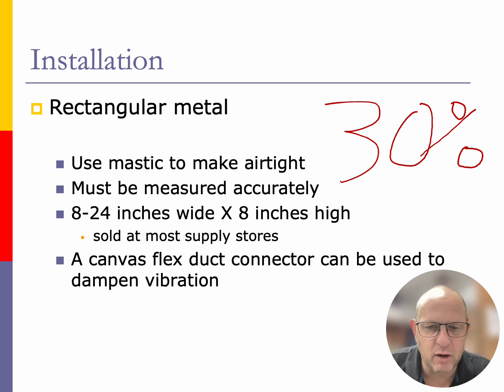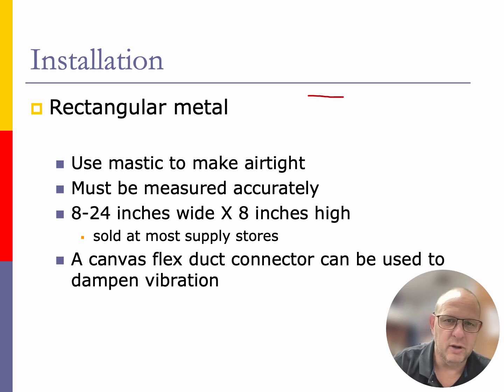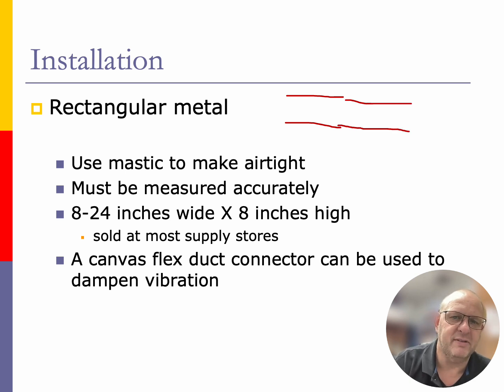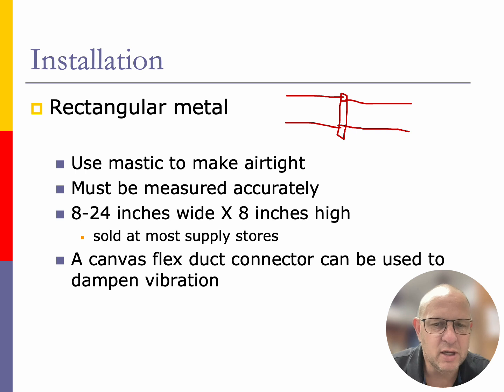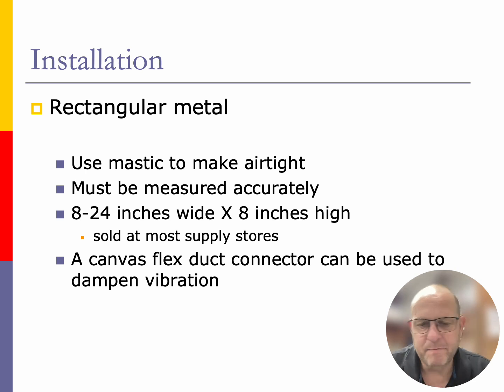Now your rectangular ductwork is going to have gaps in it, and those gaps are going to be evident where we're putting the two pieces of metal ductwork together. Now I know that we're using drive cleats on there, and when these two things are coming together, we'll have these two pieces of ductwork sitting here. We'll have drive cleats and S-lock, they'll actually overlap a tad bit, and then we'll have our drive cleats that are going in here with the tabs that are bent over. We will take mastic, which is basically caulk on a brush, and we will brush that joint with that silicone looking material, and it will cause an airtight seal to form within that ductwork, so we don't have to worry about that 30% loss in the ductwork as far as air leakage is concerned.